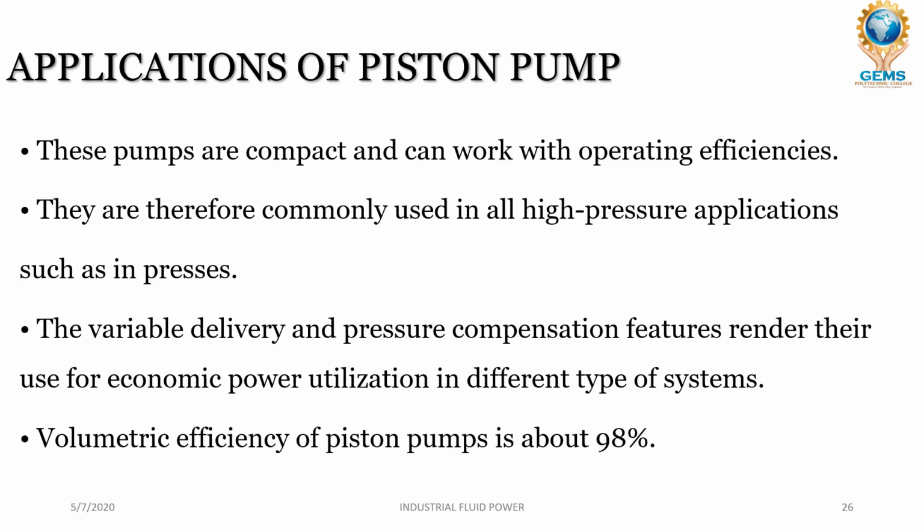Applications of piston pump. These pumps are compact and can work with high operating efficiencies. They are therefore commonly used in all high pressure applications such as in presses. In press applications, these types of piston pumps can be used. The variable delivery and pressure compensation features render them useful for economic power utilization in different types of systems, and the volumetric efficiency of the piston pump is about 90%.